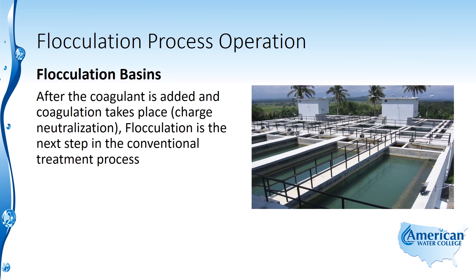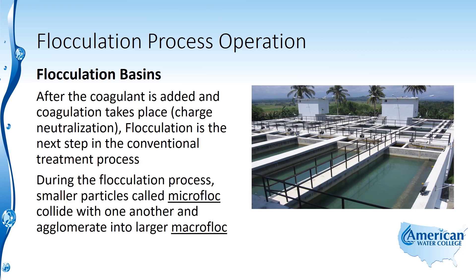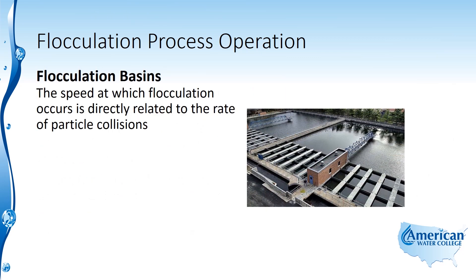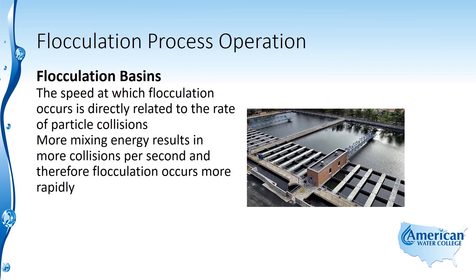After the coagulant is added and coagulation, or charge neutralization, takes place, flocculation is the next step in the conventional treatment process. During flocculation, smaller particles called microfloc collide with one another and agglomerate into larger particles. The speed at which flocculation occurs is directly related to the rate of particle collisions. More mixing energy results in more collisions per second, and therefore flocculation occurs more rapidly.